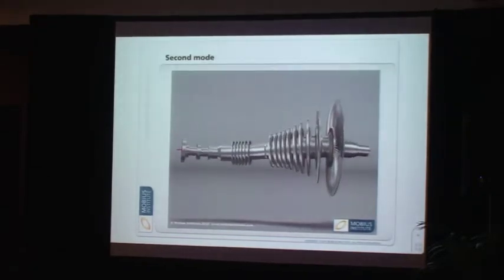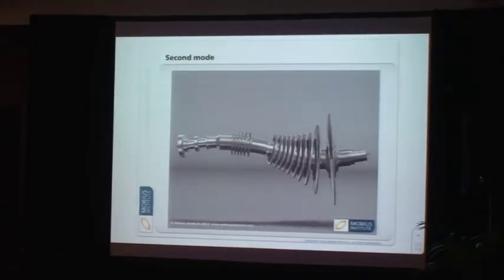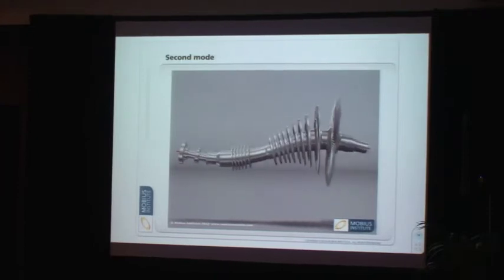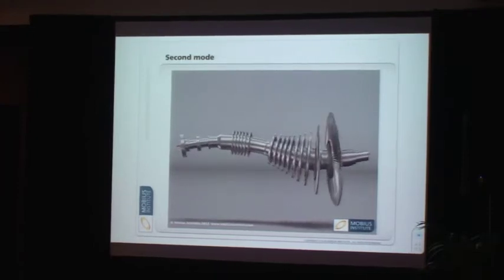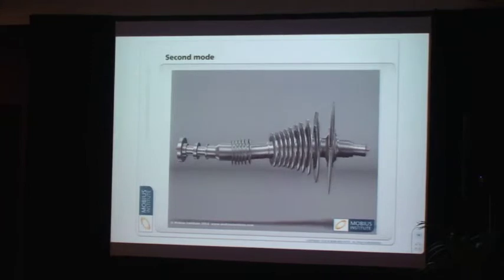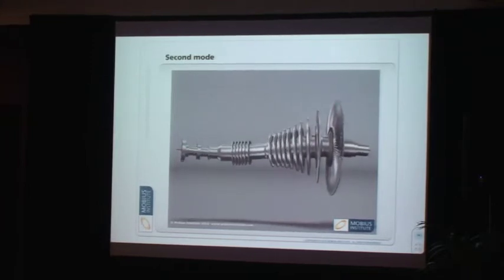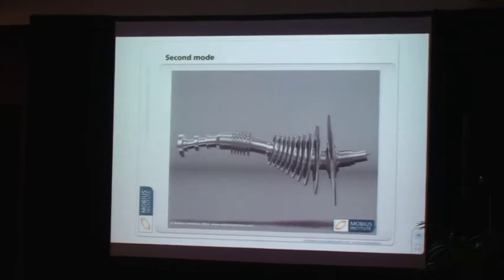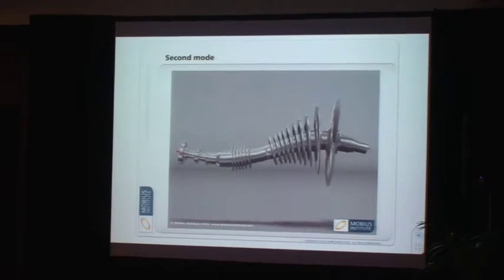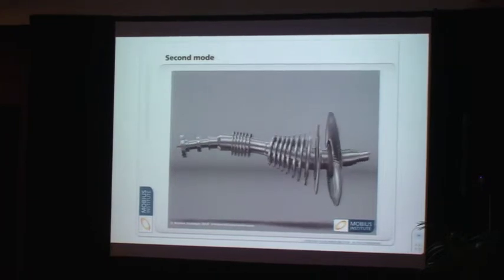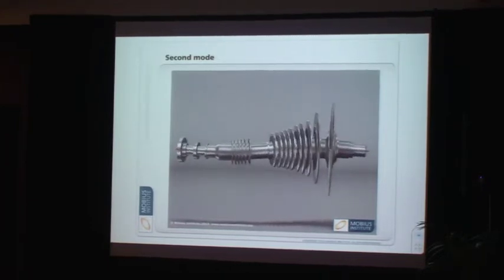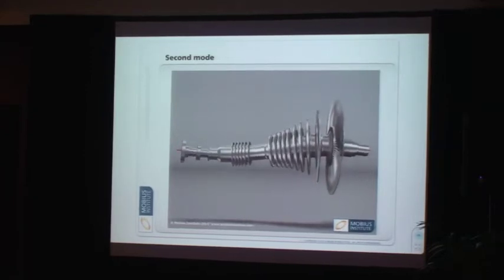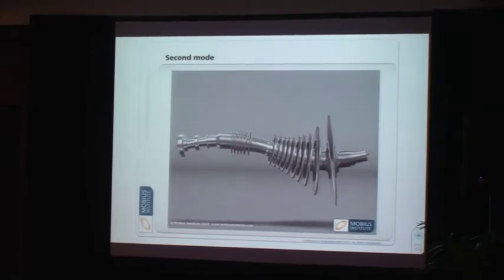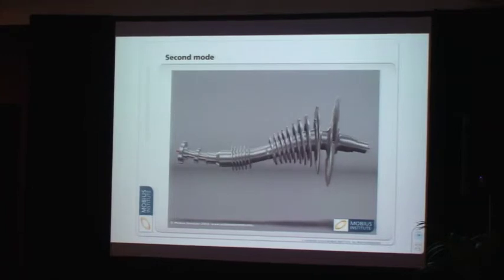As we get more into it - I'll come back to this towards the end of the presentation - if you saw Simon's demonstrator out there, we had the first mode, and this is the second bending mode, and that is in effect what the machine is doing when you run it up above that second critical. But how do we know what it's doing? That's what the vibration readings tell us - that's what the orbit really tells us.